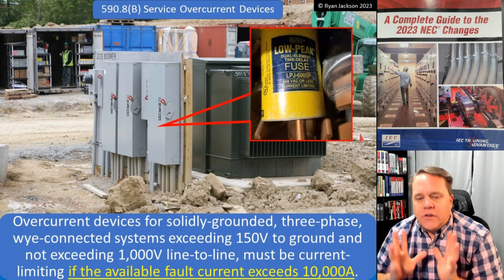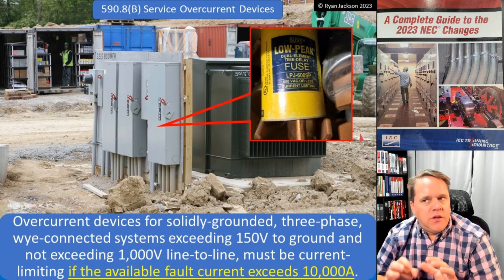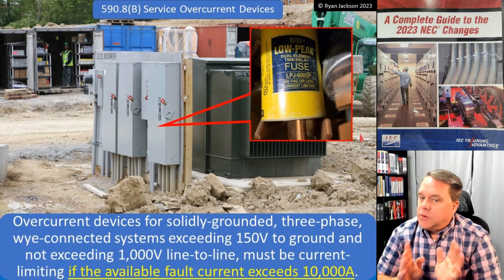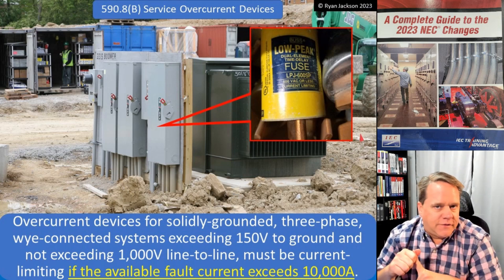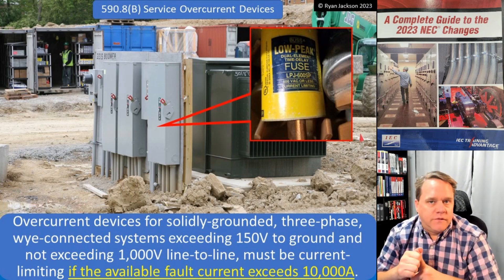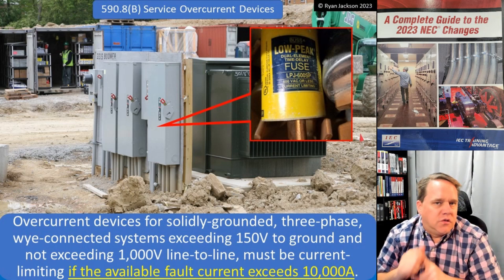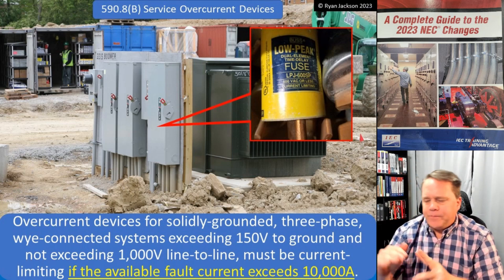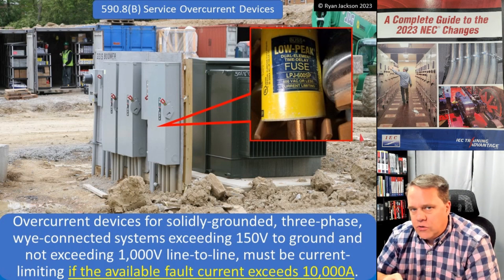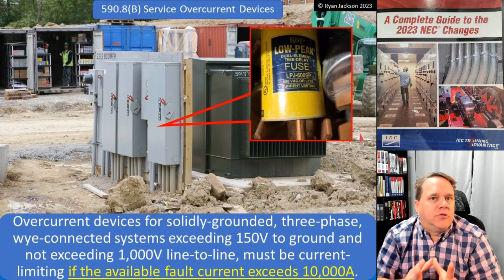Exceeding 150 volts to ground, not exceeding 1,000 volts line to line. Here in America, the only voltage system that really fits into that is 277/480. This only applies to Y-connected systems — it wouldn't apply to a 480-volt corner-grounded system, since that would be 480 volts to ground and this is only for Y-connected systems. So here in the States, we're talking 277/480. If you're in Canada or areas very close to Canada, you might see a 347/600-volt, three-phase, four-wire Y. Either of those would fall into the voltage parameters of this requirement.